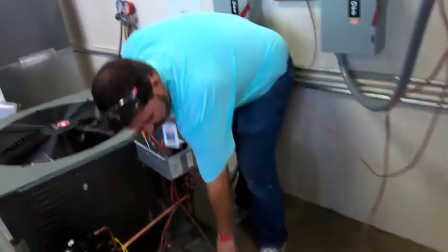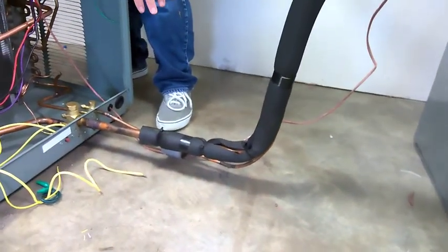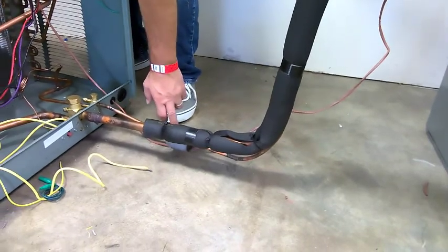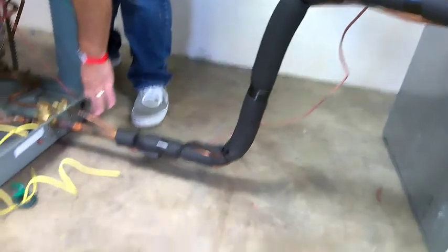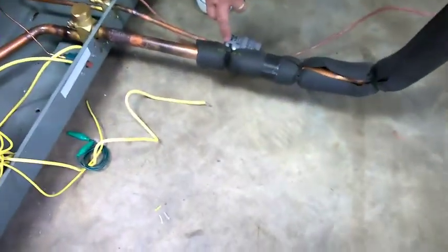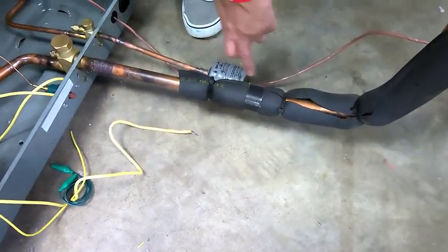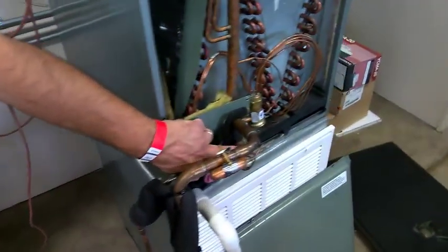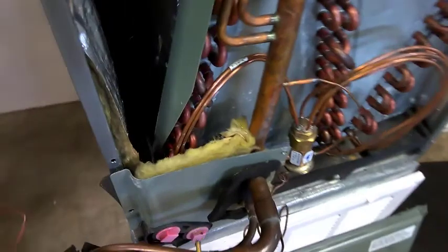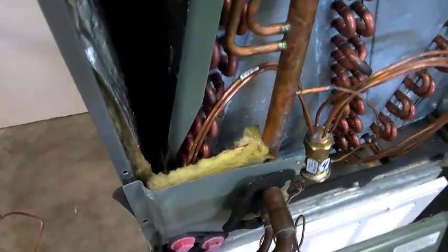You'll trace it out. It goes through a filter dryer, which dries any moisture that may have been in the system. There should be none, but if for any case there was, that would help dry it out, as well as any small debris. Again, good piping practices should keep that from happening, but if you have any small debris, that will catch it. But this liquid flows all the way until it hits that metering device. That particular metering device is called a TXV.